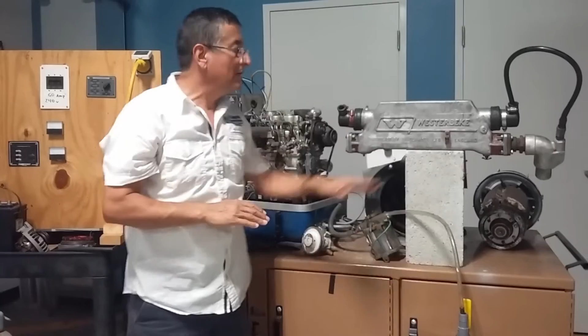This is the level of the water line, and this is the reference that you can use to install the generator. What happens if, for some reason, you only have space in that corner to install the generator? And of course, that corner is over the water line. In other words, the raw water pump will be located over the water line.